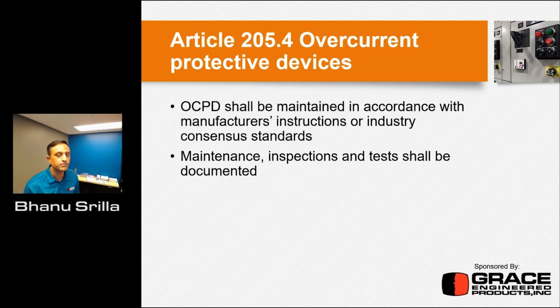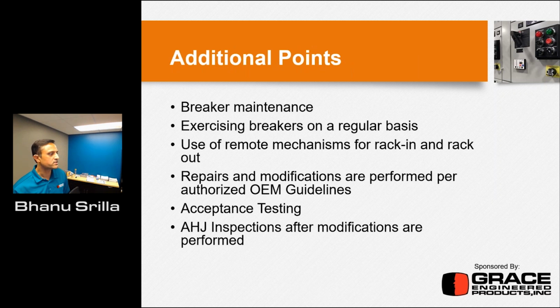Okay, so just make sure the importance of documentation is very critical, that while doing all these things, you need to maintain the documentation as it relates to that. Okay, so additional points, you need to make sure the breaker is maintained properly, exercising the breakers on a regular basis per the manufacturer guidelines again, right? And the use of remote mechanisms, because there are a lot of remote mechanisms available for breaker rack in, rack out, so you don't need to have your personnel physically interact with it within that restricted approach or limited approach boundaries. You can just have them do this from a far remote area that will minimize the exposure to that hazard.